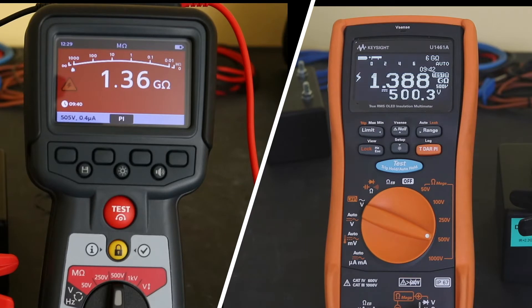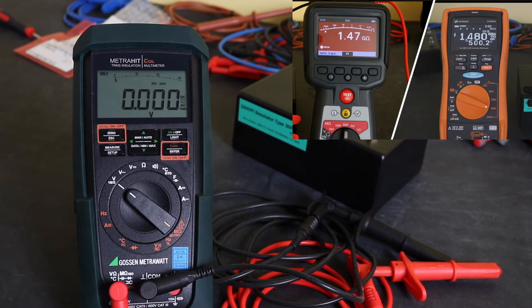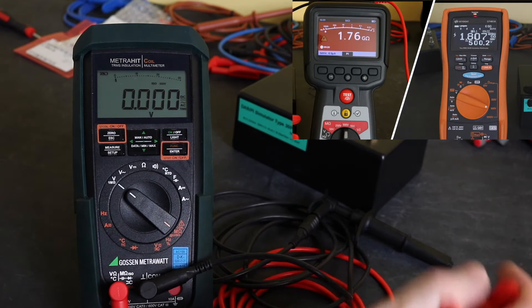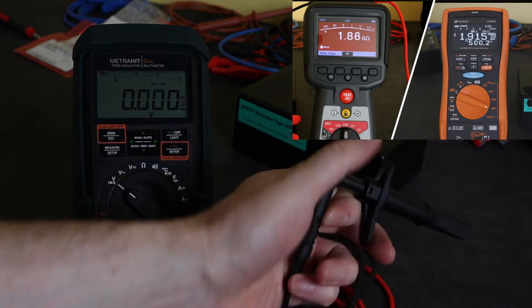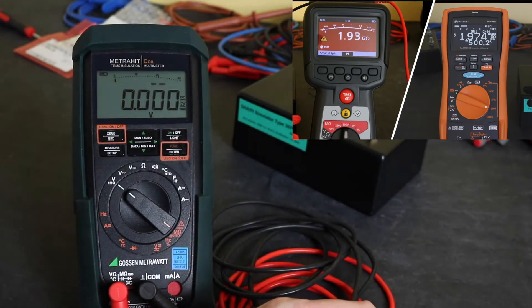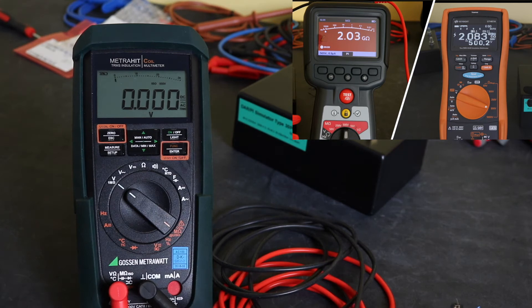I'm going to leave this test running whilst I take a closer look at the PI test function on the meters themselves. Some of you will notice that the Gossen Metrahit Coil is missing from this test. The first reason is that the maximum range on an insulation test for the METRAHIT is 3.1 gigaohms, and the polarisation index simulator I've got will actually go above that, up to around about 14 gigaohms by the end. So it's outside the range of the Metrahit Coil.